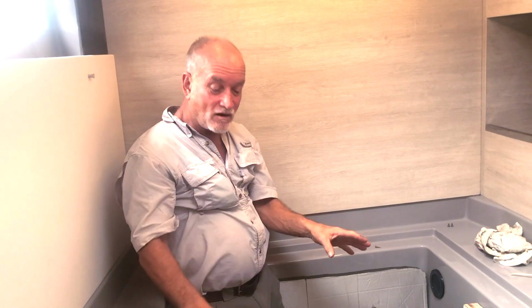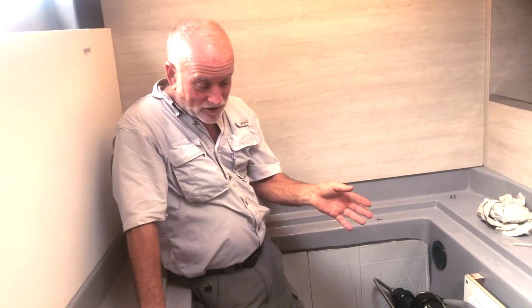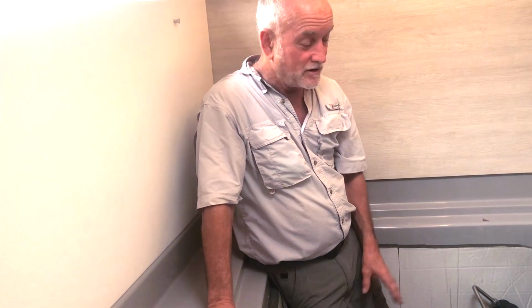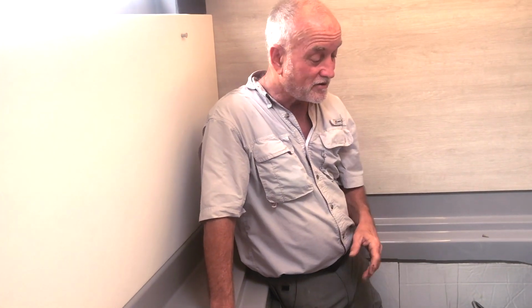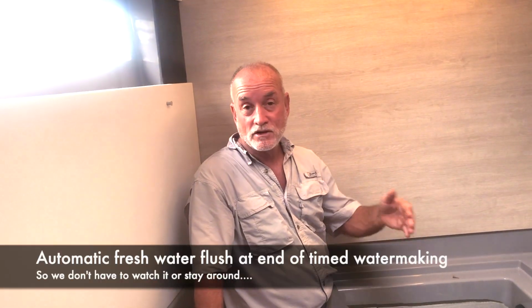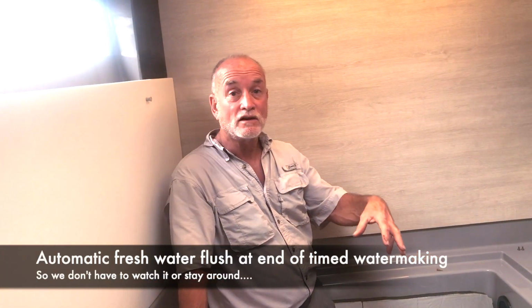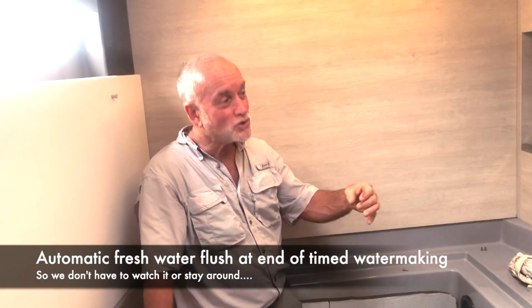Okay, so basically you've got all 3 pumps. Once the system's running, we program it to run, let's say for example, for 4 hours. We'll do that from the control panel up front. You'll run it for 4 hours, and then you can go fishing and do whatever you want after that. At the end of the 4 hours, it's going to stop and automatically freshwater flush itself.